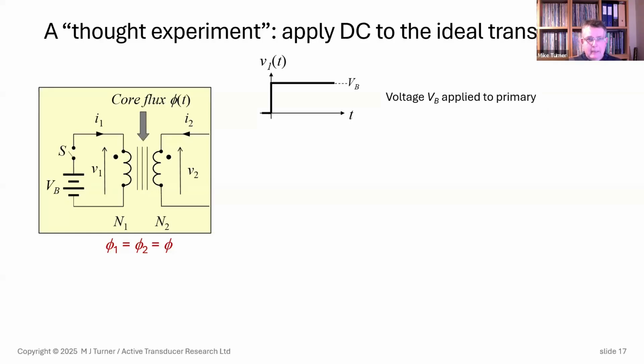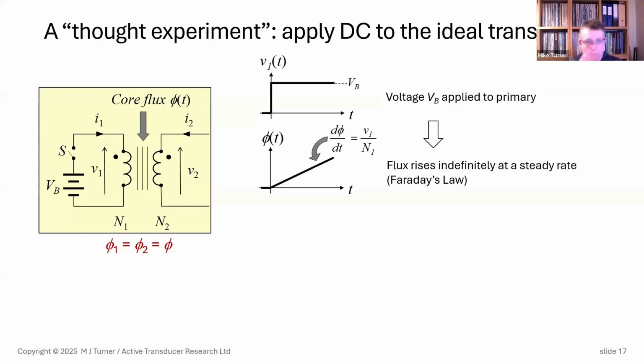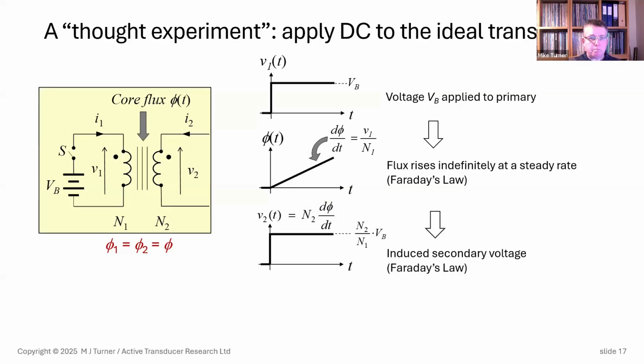What happens next? Well, we remember Faraday's law. Flux rises at a rate determined by the voltage, so dphi by dt is constant. We have constant voltage on the winding, a steady rate of rise of magnetic field, and the flux will carry on rising indefinitely, because there's nothing to limit it, there's no resistance in the circuit, and no limit on the amount of flux density the core can carry.